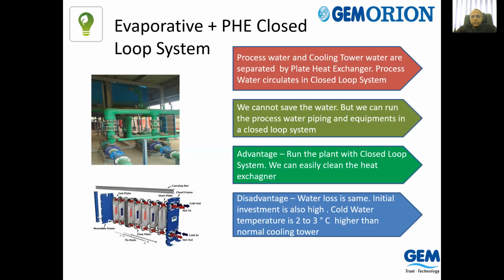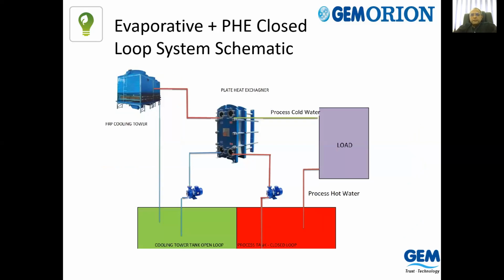There has to be some approach between the cooling tower water and the internal water. So this way also you can avoid scaling in the mother machine and your internal process, but evaporation losses will remain the same because the heat removal is directly proportional to the sensible heat removed, or it depends on the evaporation of water. So this is the typical system where we can see the cooling tower water circulating between the heat exchanger and the cooling tower. So this will have scaling and evaporation, whereas this will be in closed loop and you will not have any evaporation. This will avoid scaling as well as downtime in your mother machine, which is more valuable to protect. But here scaling will happen in the heat exchanger, so cleaning of the heat exchanger is a must.